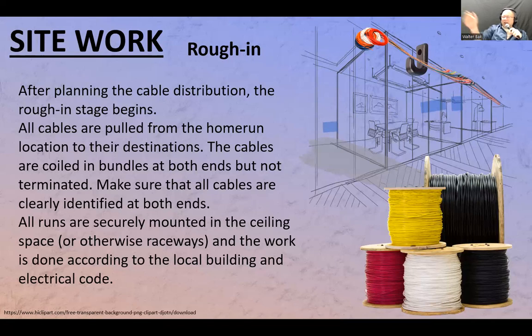Here's your pathway. Along the pathway, you mount the J hooks every 4 feet, no further than 4 feet apart, so the wires don't snag too much. Then you bring that string into the J hooks so you can mount the wires on one side to the string, and you can pull the string on the other side, and with one pull you can get all those. Now you might want to tie something called a back string to the wires so you can reuse that pathway if you want to do more pulls.